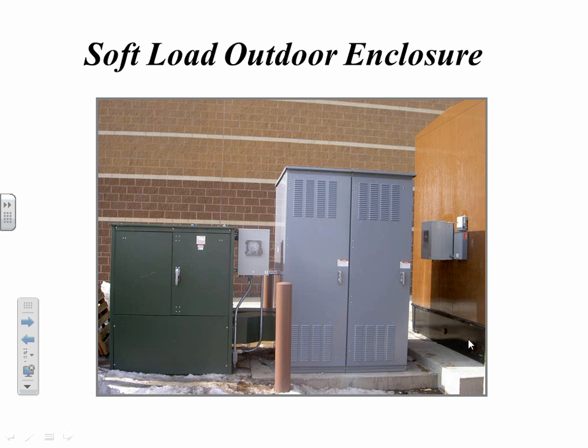Here again is what it looks like sitting out in the parking lot. You wouldn't really notice anything different or sophisticated there. But again, the transformers are over here, and this is just a transition cabinet being fed into the switch. And of course, the generator is coming underneath here and hitting the generator terminals. Very clean operation, no difference on the inside of the store at all. Typically, you want to do these when the store is being built if you can.